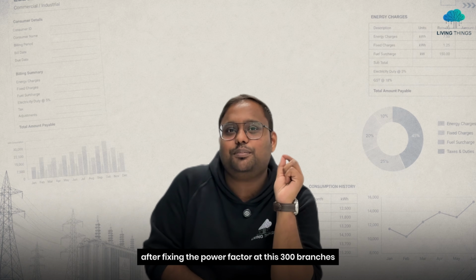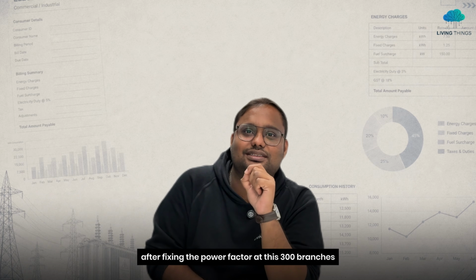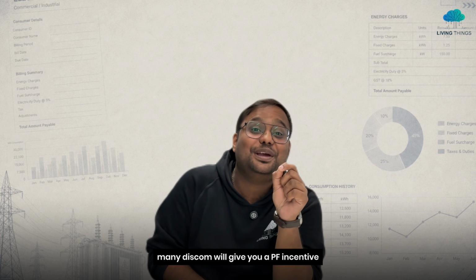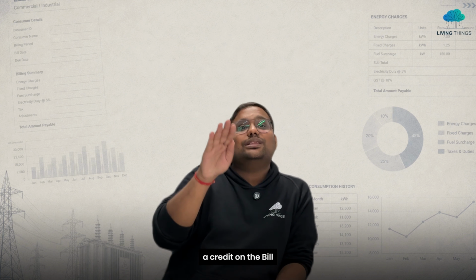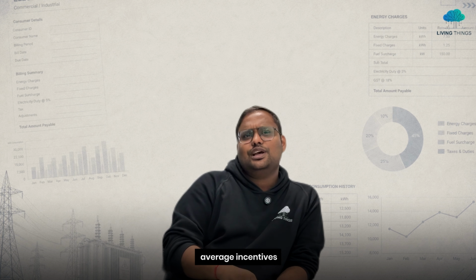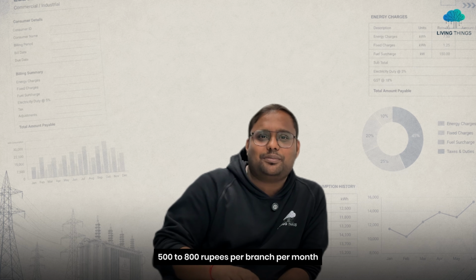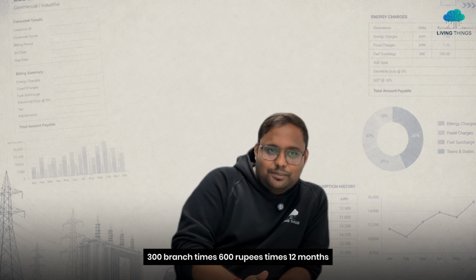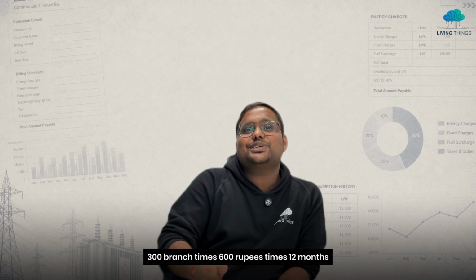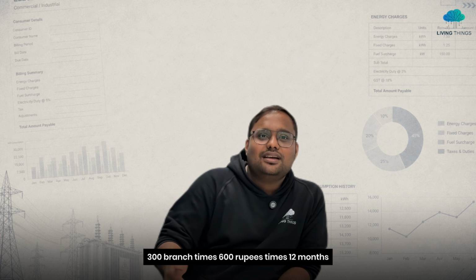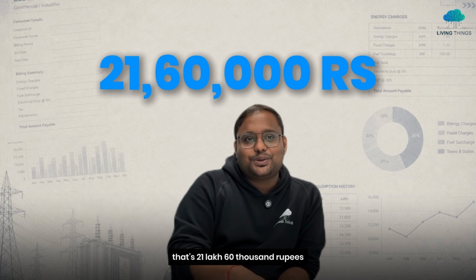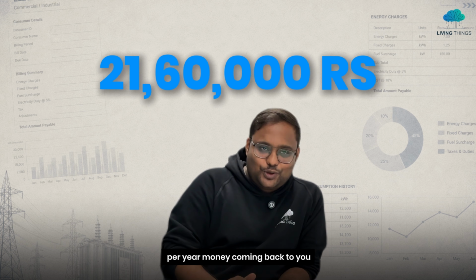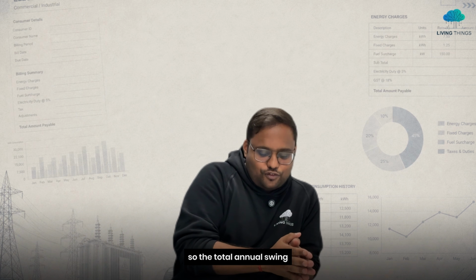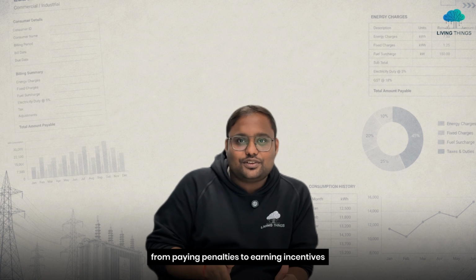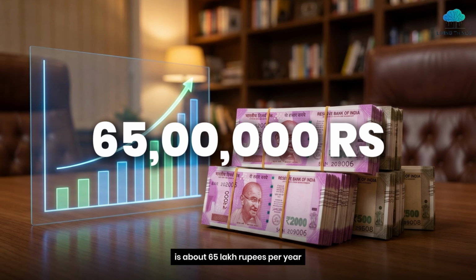Now flip it. After fixing the power factor at these 300 branches, let's say they all go above 0.95, many DISCOMs will give you a PF incentive, a credit on the bill. Average incentive is 500 to 800 rupees per branch per month. Let's take 600 rupees. 300 branches times 600 rupees times 12 months, that's 21,60,000 rupees per year, money coming back to you. So the total annual swing from paying penalties to earning incentives is about 65 lakh rupees per year.